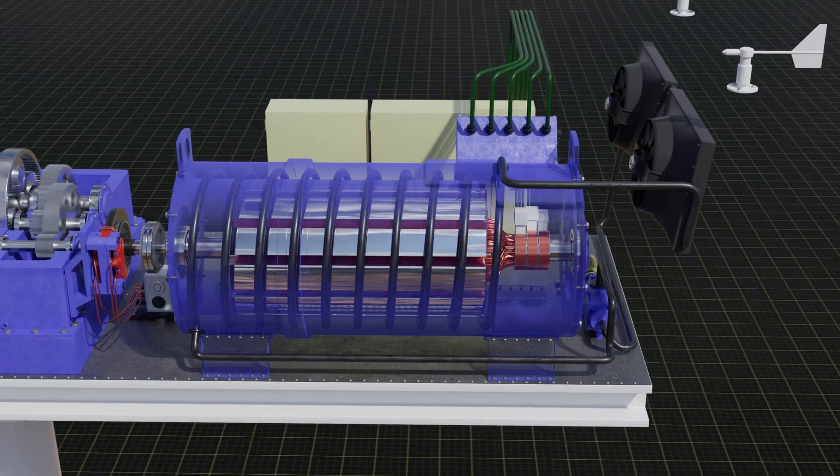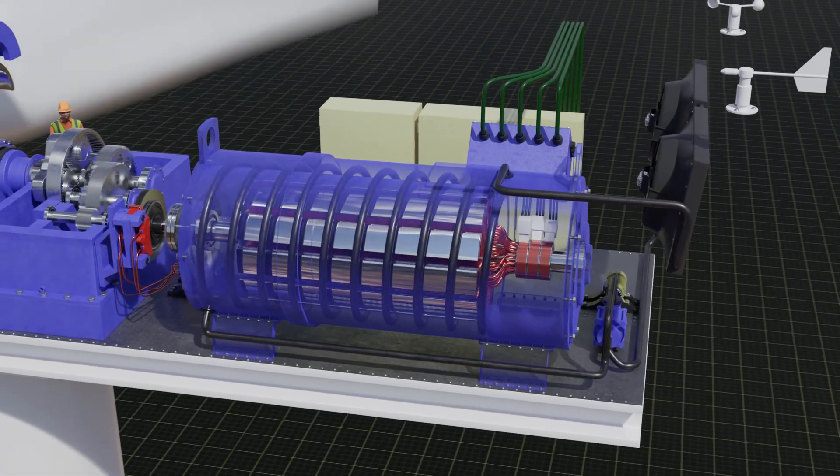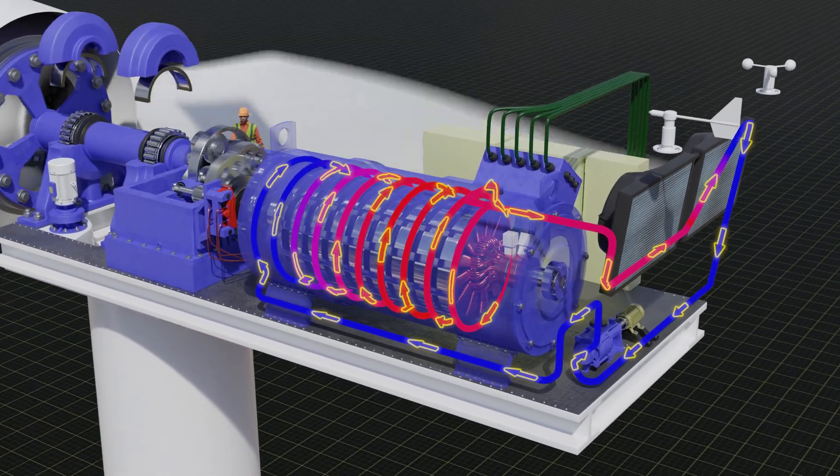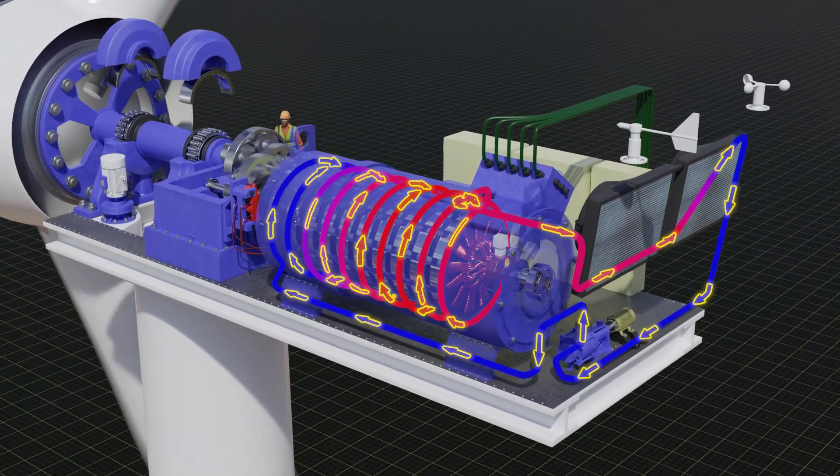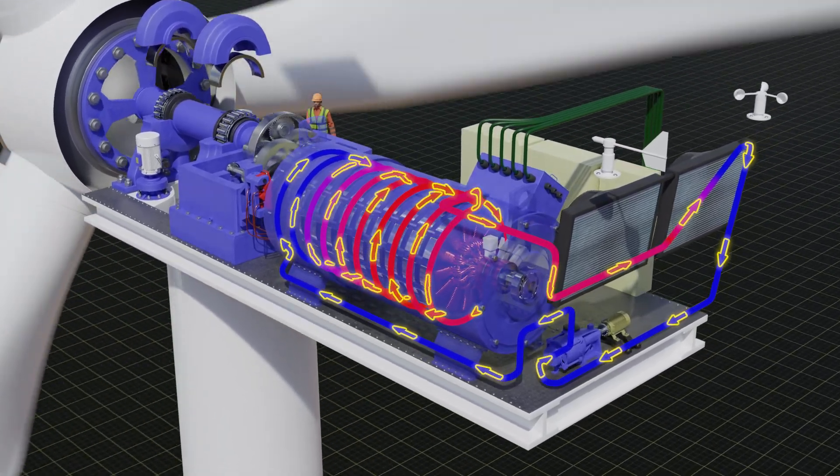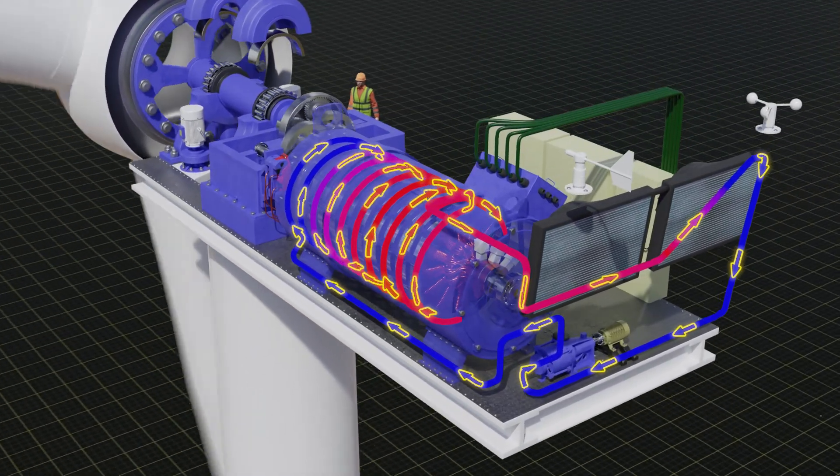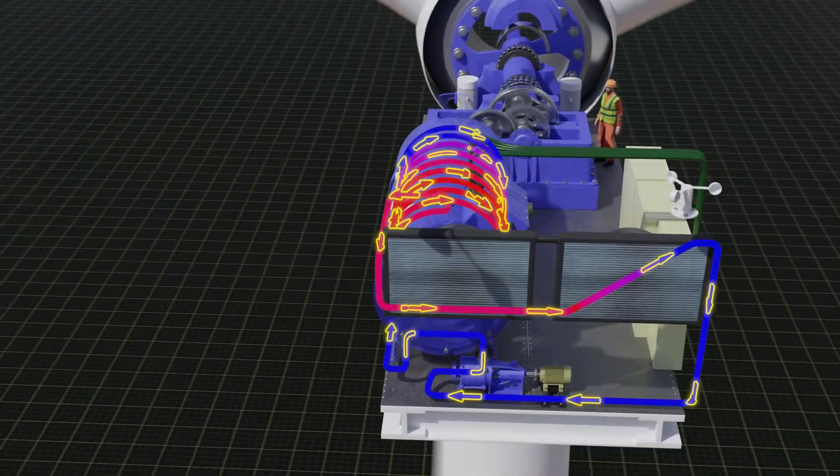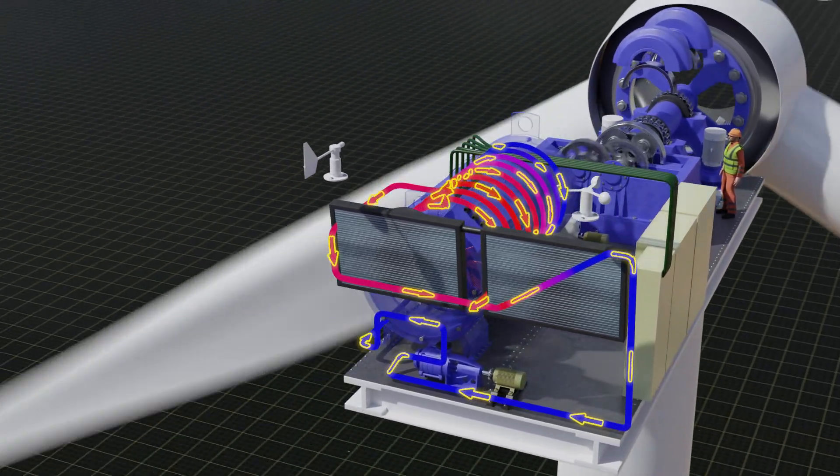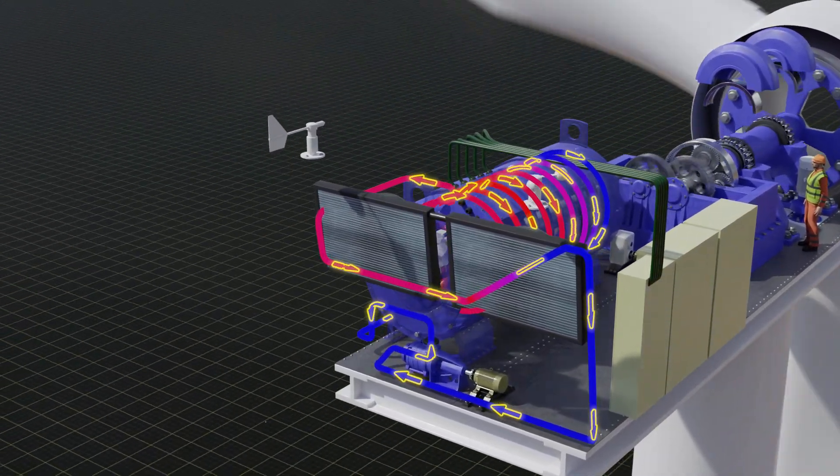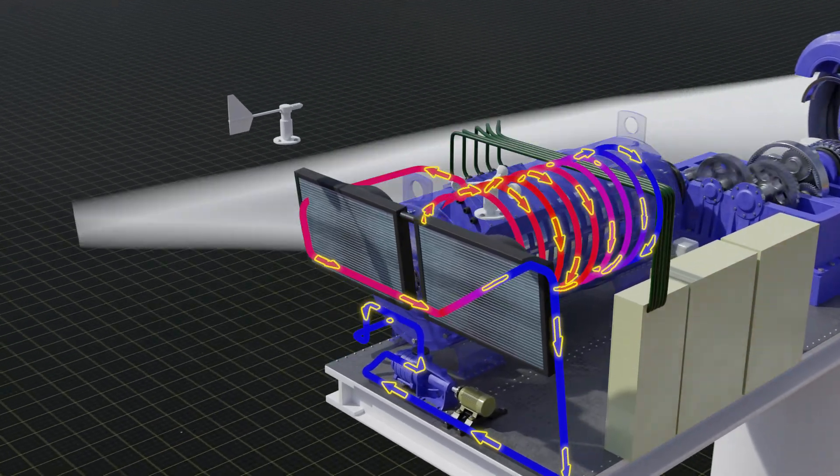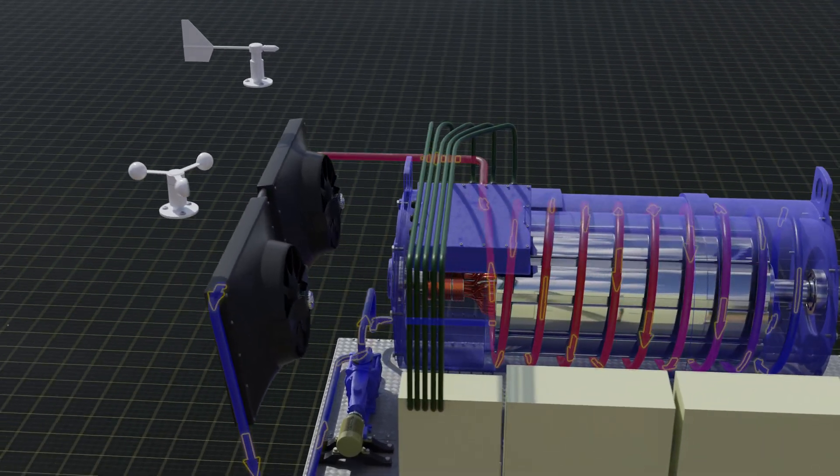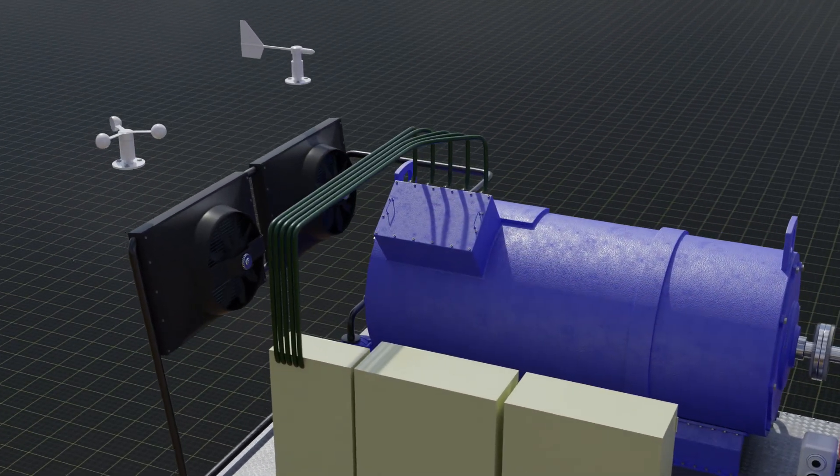While generating electricity, the generator heats up, so it needs to be cooled. This powerful turbine uses liquid cooling of the generator. The coolant is pumped by a pump into special cavities in the generator. Inside the generator, the fluid is heated, then it passes through the pipes to the radiators where it is cooled by fans. From the radiators, the fluid flows back to the pump, and so on in a circle. Less powerful turbines do not have a liquid cooling system. In such turbines, the generator is simply cooled by air with a fan.